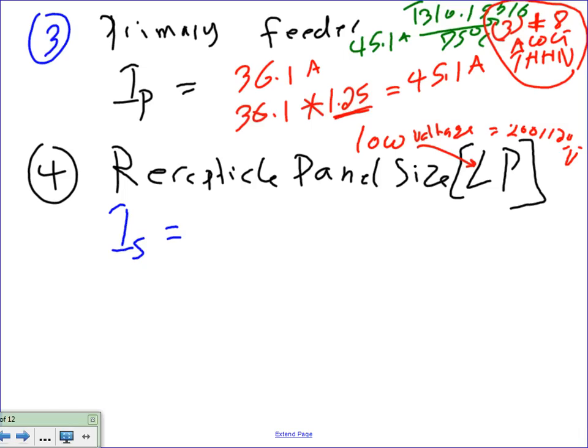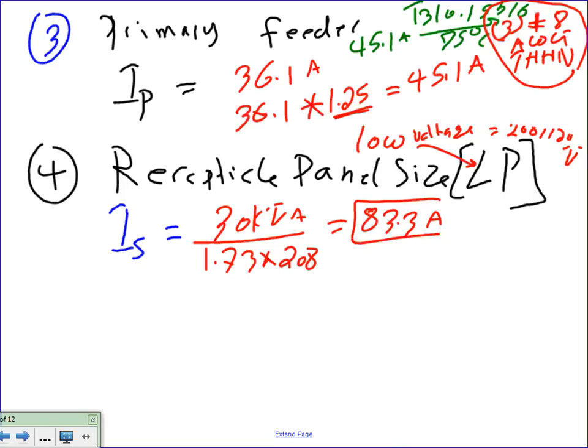On the secondary side, Chris, let's do this. On the secondary side, I know the full load current secondary without even looking at it, it's 83.3. But I still would like you guys to do it. So 30 kVA divided by 1.73 times, now we move to the secondary, 208. If you do the math, give or take, that will be 83.3 amps. Now the same thing. I'm sizing the receptacle panel now. I'm using this secondary current to size the receptacle panel, the low voltage panel 208/120.